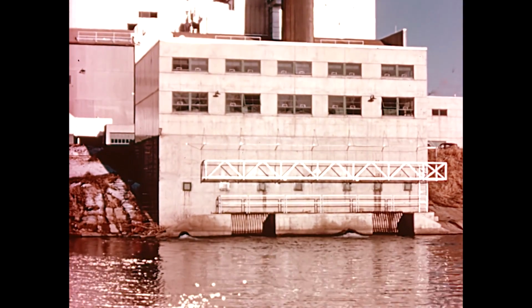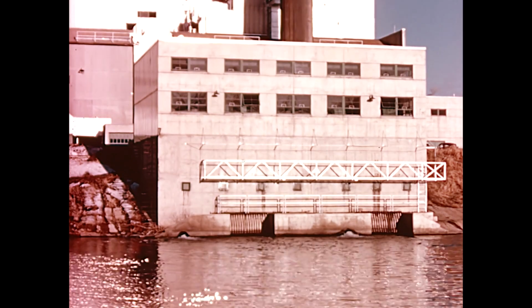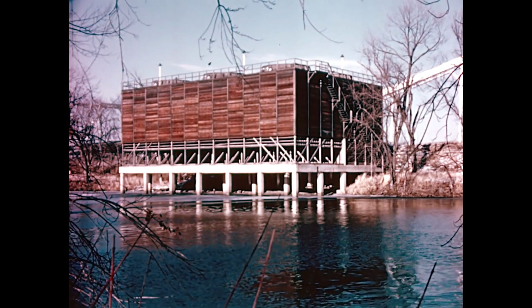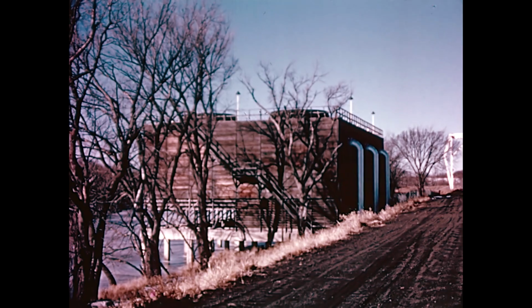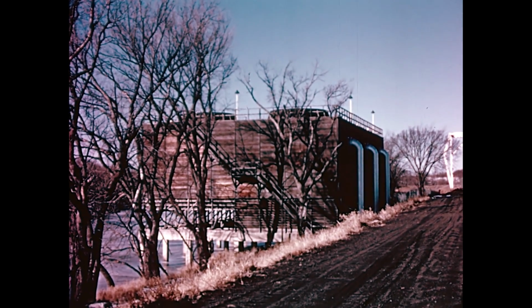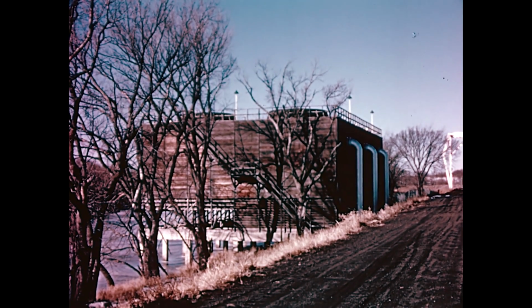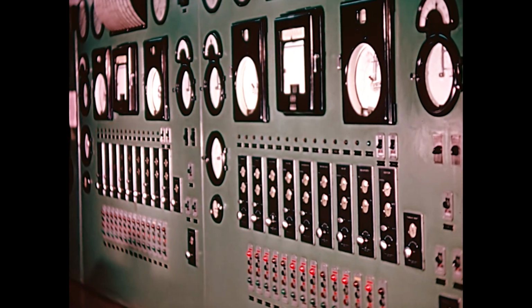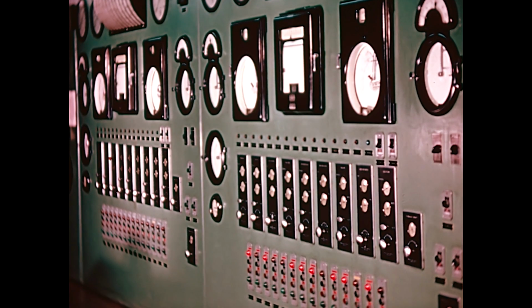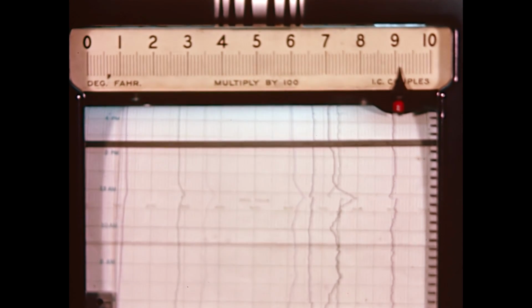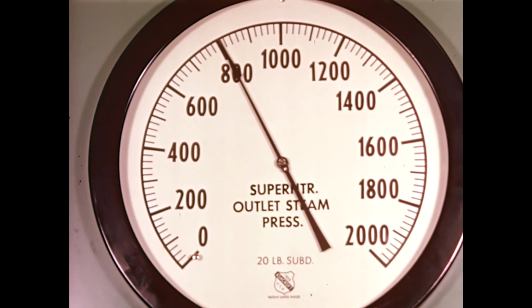River water is used to condense the steam. When all units are running, there is need for 61,000 gallons per minute. A cooling tower provides for lowering the temperature of the water before it returns to the river so it will not raise river temperature more than 10 degrees. The steam, when it leaves the boiler, has a temperature of 910 degrees and a pressure of 800 pounds per square inch.